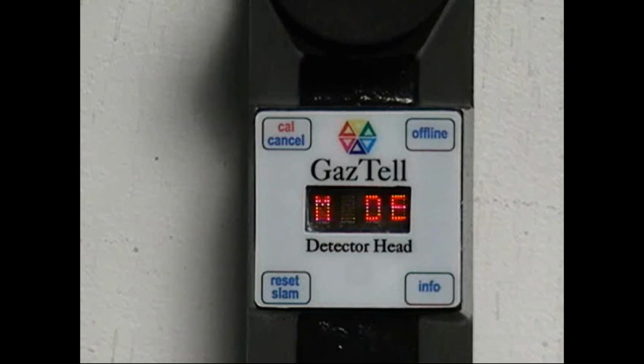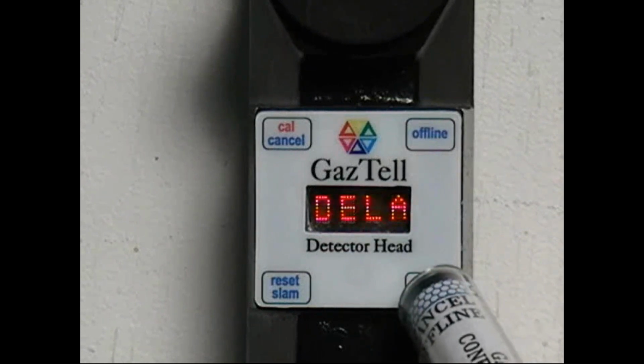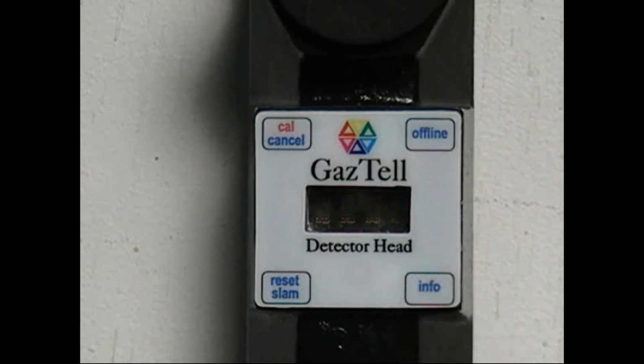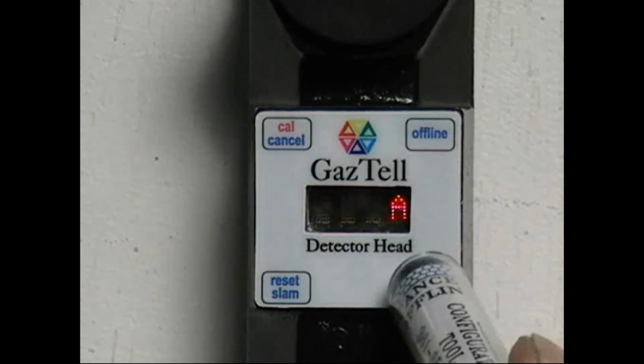The next item in the information display is the alarm delay. Here is where you can choose to delay an alarm by up to 5 seconds. This is often used where users want to be sure the concentration of gas is present long enough to warrant triggering the relay. As you can see, if you don't hold the magnet over the info mark long enough for the 1 second, it will ignore the command.